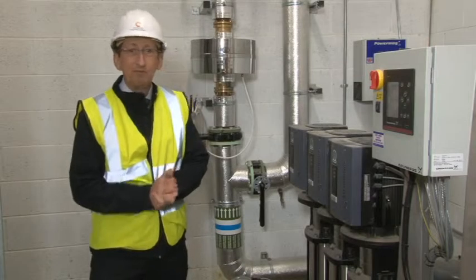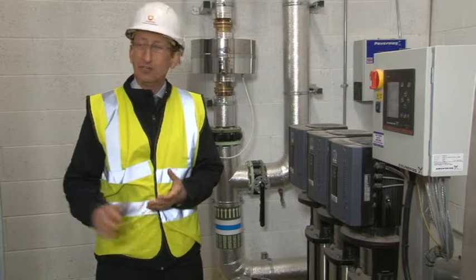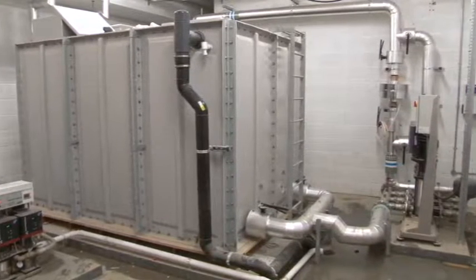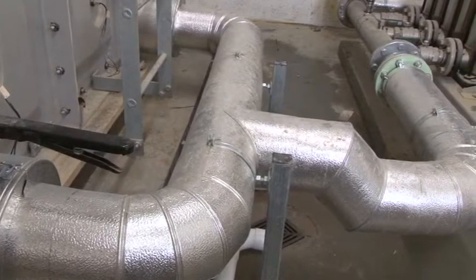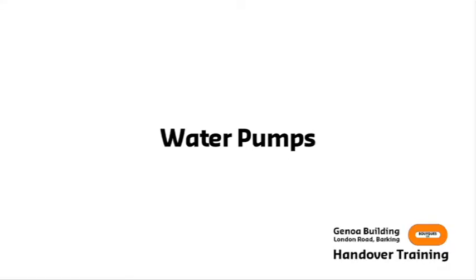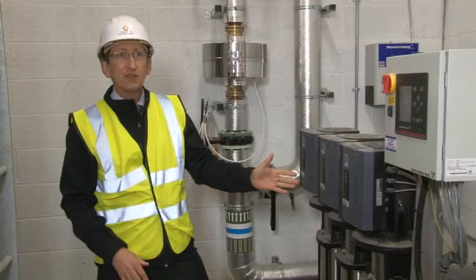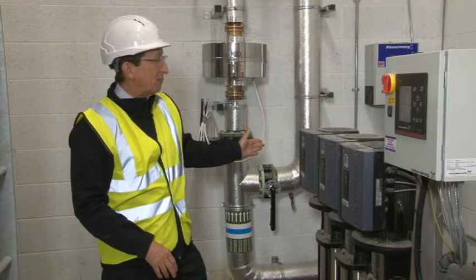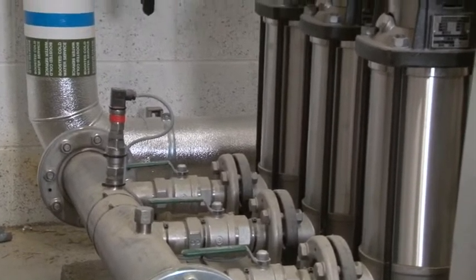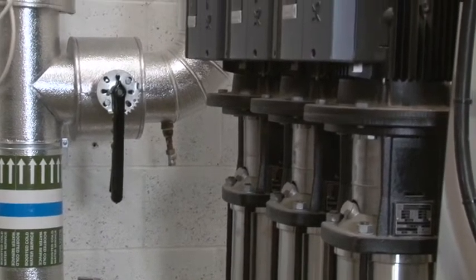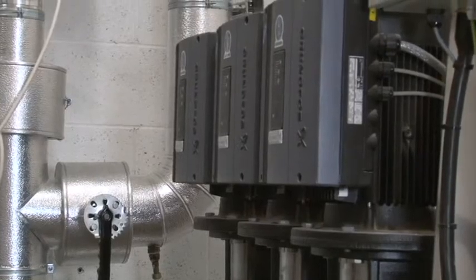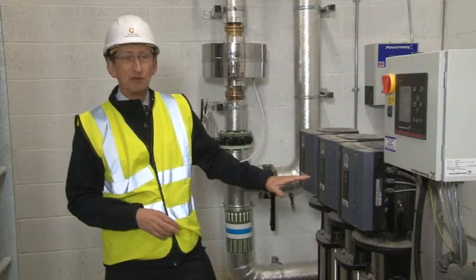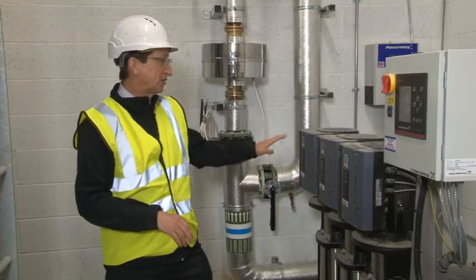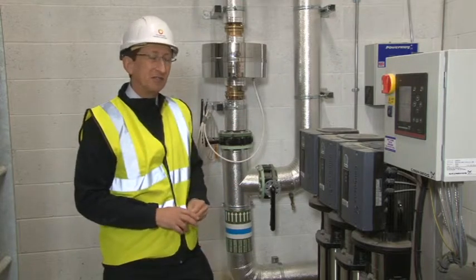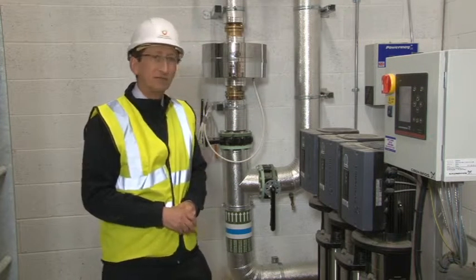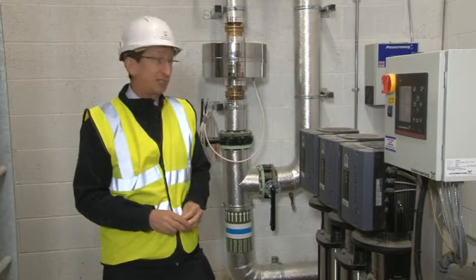Excellent. So what we've got, basically we're in the tank room for the cold water supply for the building. So that's what we've got here. Obviously that's the main cold water tank. So the cold water supply is feeding into there, out of the tank to the booster set. So we've basically got 3 pumps within the booster set. So basically it'll just ramp up as demand for cold water in the building increases. The more pumps will come on. So we've got basically a duty assist pump set. So we've just got 1 pump modulating off and on, just a very small amount of water usage at the moment. If a lot of people turn the taps on, then you might get 2 pumps running. If we're running flat out, the third one might well then kick in to supply enough pressure to get cold water up to the furthest flat, should demand dictate.